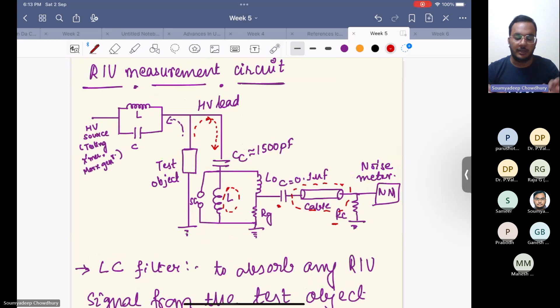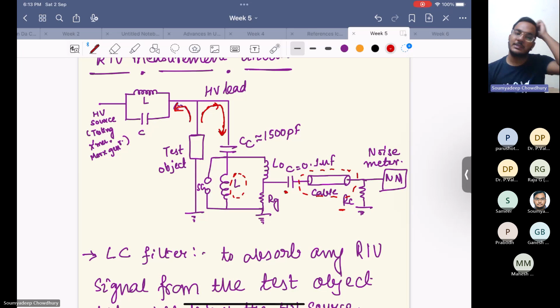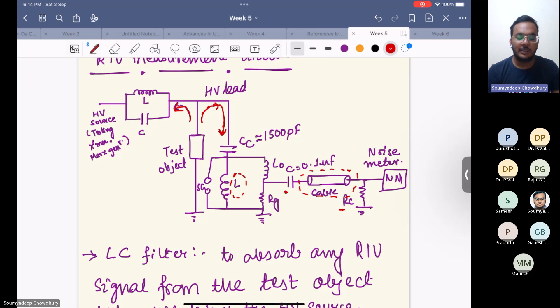This LC filter is present to absorb any RIV signal from the test object. The test object emits the RIV signal, and this signal has two paths - one is this red path shown here, and the other is this second path. My measurement circuit is in the right half, so we want the entire RIV signal to travel to the right half of the circuit. Hence we place an LC filter on the left half near the source, so that these RIV signals - which are high frequency signals - don't destroy our high voltage source, the testing transformer or the Marx generator. To avoid that, we use an LC filter.